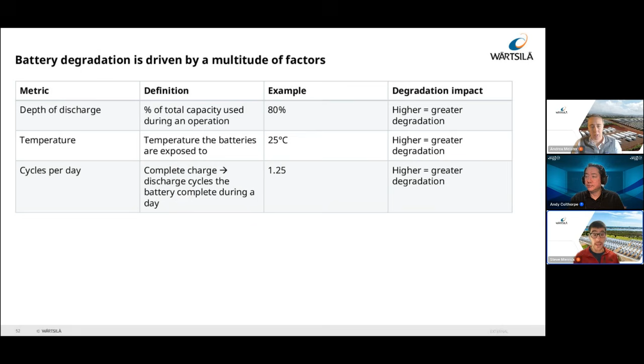And then cycles per day: the number of complete charge-to-discharge cycles the battery completes during a day. If the battery goes from 100% down to 0, that's 1 cycle. If it goes from 50% down to 0, that's a half cycle. If in the same day it goes from 50% down to 0% again, that's another half cycle, adding up to 1 full cycle that day. So you can have lots of smaller operations that add up to the total number of cycles per day.